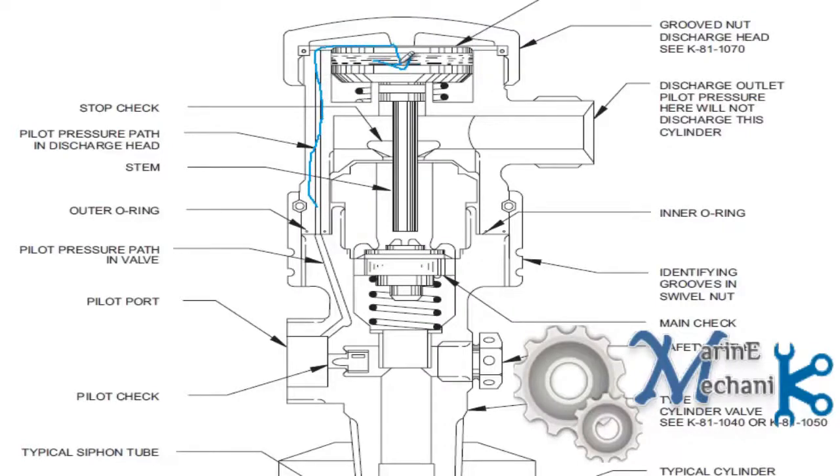Alright, so as the pilot CO2 through this channel pushes the piston down, the stem also moves down along with the piston, tapping the main check valve here, and as it is tapped, it moves down against the spring force. And then the CO2 comes here. Similar to the boiler safety valve, we have a lip-like arrangement, the curve. The CO2 from the main bottle, I'll change the color and explain, comes here, it travels like this and then gives a push here, thus enabling the valve to open more.